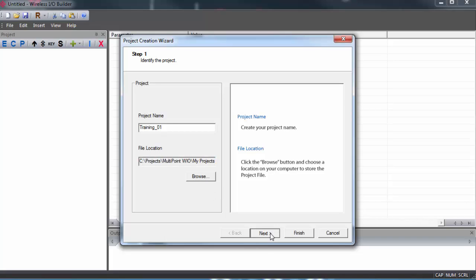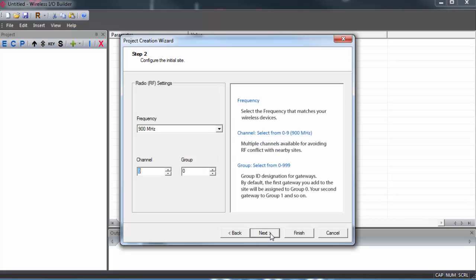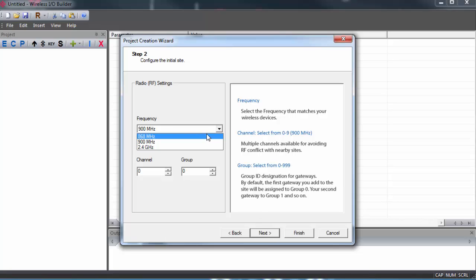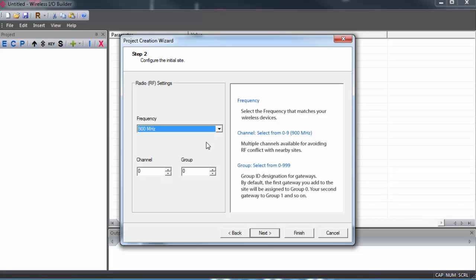We'll select the frequency, and there are three different frequencies available. Be sure to pick the frequency that matches the radio in your gateway. In my case, I'm using the 900 MHz model. By default, the channel is set to zero. It's good practice to always select a different channel just to minimize the chances of crowding the same channel.